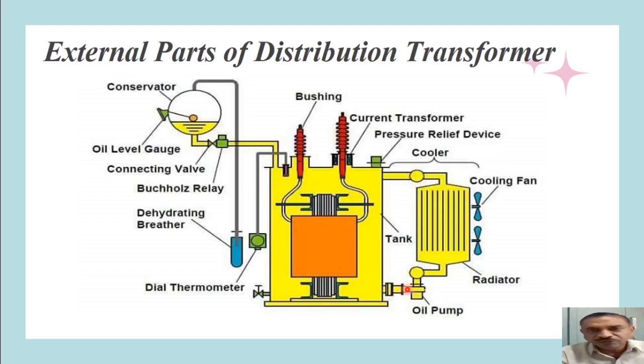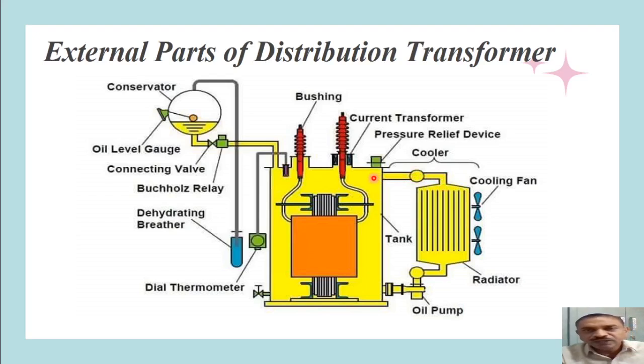On the right side of the figure, at the bottom, there is an outlet that goes to an oil pump. The oil pump forces oil coming from the bottom of the tank through a radiator. The radiator is a device that cools down the oil. The pipes or ducts carry the heated oil through the oil pump. External cooling fans fitted on the radiator provide a flow of cool air on the radiator and its fins and pipes, thereby cooling down the oil inside. This cooled oil is then passed back to the transformer tank.